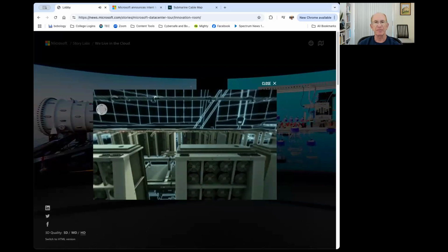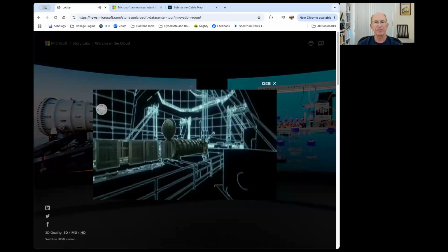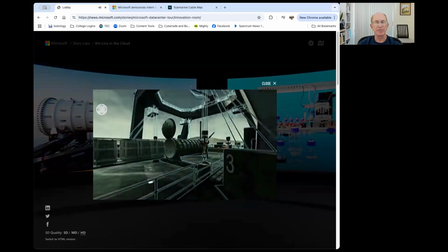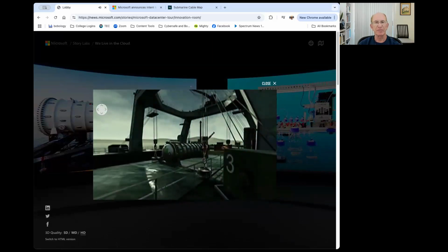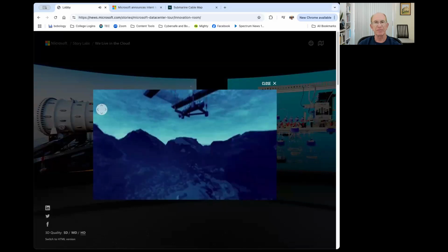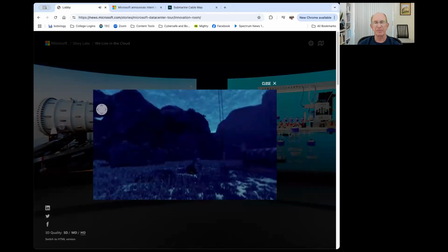Natick's equipment failure rate is 1/8 the rate of data centers on land, where corrosion, temperature fluctuations, and human contact contribute to error. The Natick capsule is filled with nitrogen, which causes less damage to the servers over time than oxygen. Reliably cold underwater temperatures conserve resources by cooling the servers and helping to optimize energy usage.